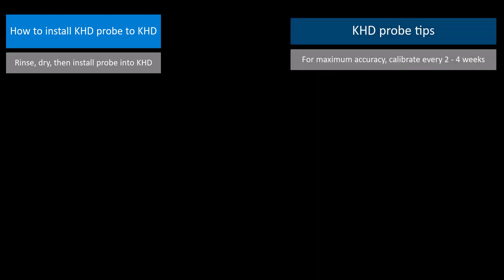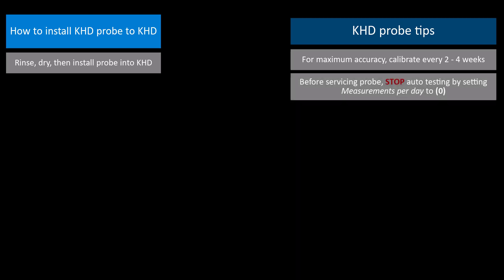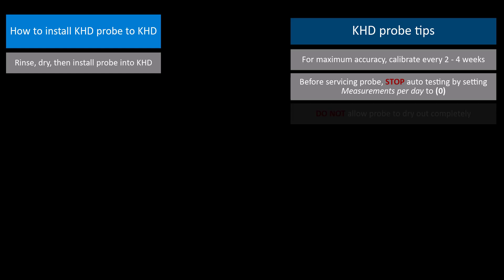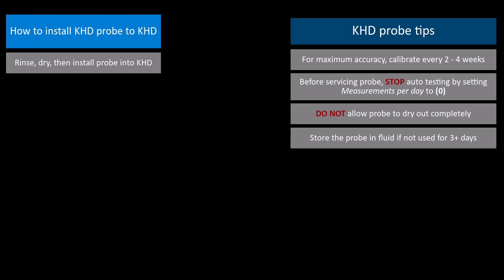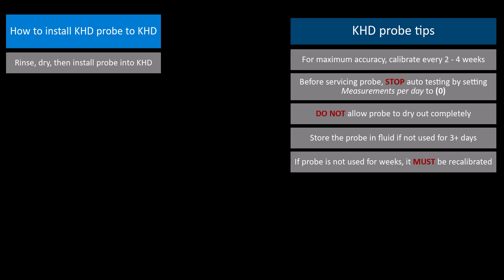To get the highest accuracy out of your KHD, we recommend you calibrate the probe every two to four weeks. Anytime you need to service the probe either to calibrate or replace, make sure you stop automatic KHD testing by temporarily setting the measurements per day to zero. It's also important to note the KHD probe must never be allowed to dry out. If your KHD Director does not perform any tests for more than three days, we recommend removing the probe and storing it in liquid until you are ready to use it again. The KHD will always store a small amount of water inside the measuring cell to prevent the probe from drying out. With each test, this fluid is flushed out and replaced with new water. Lastly, a probe that has not been in use for more than a few weeks should always be recalibrated before being put to use.